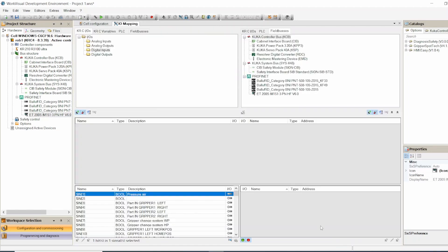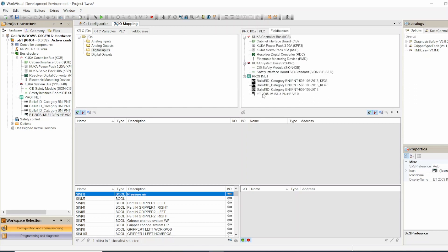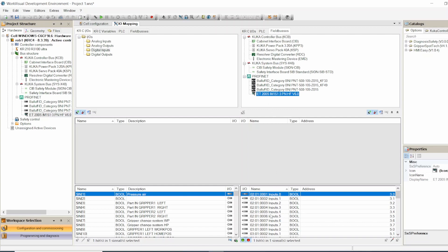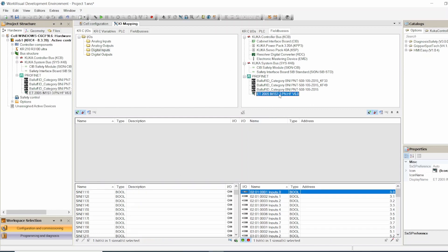Now you go to the IO Mapping to map those inputs and outputs between the KUKA and the ET200. On this side, make sure you are in Fieldbus and then select the ET200. Now down here it shows you all the inputs and outputs on this ET200 module. On the left side, make sure you are in the robot side — KRC, that's the controller — and select Digital Input or Digital Output. For now we're going to map the inputs of the ET200 to the inputs in the KUKA.